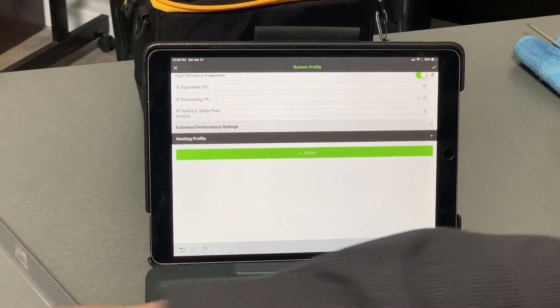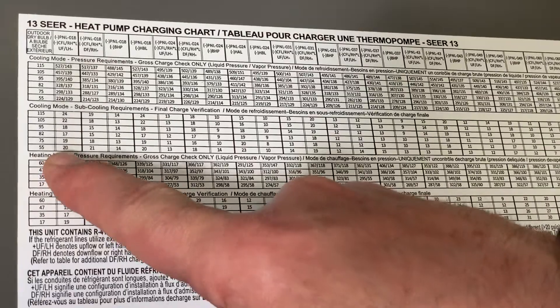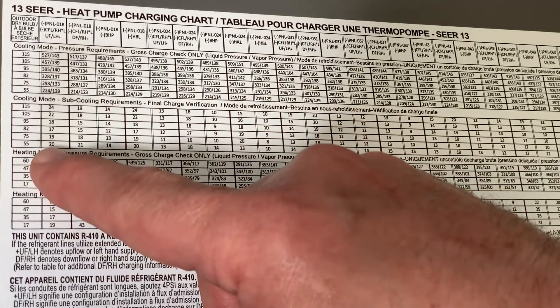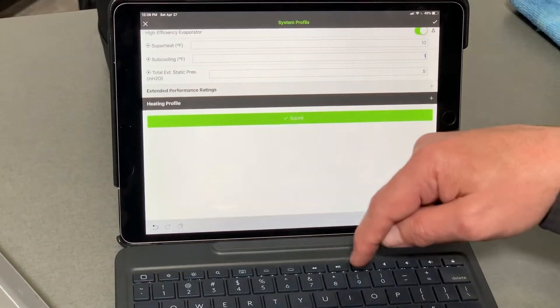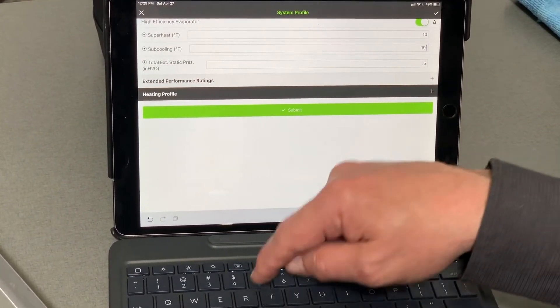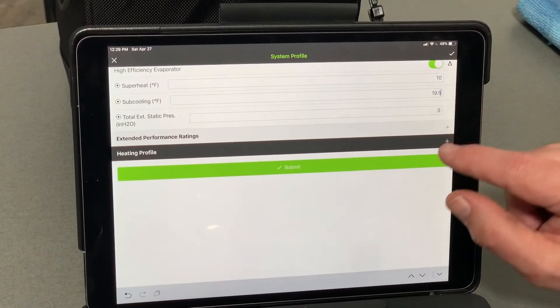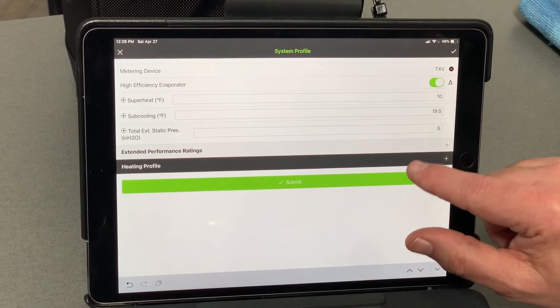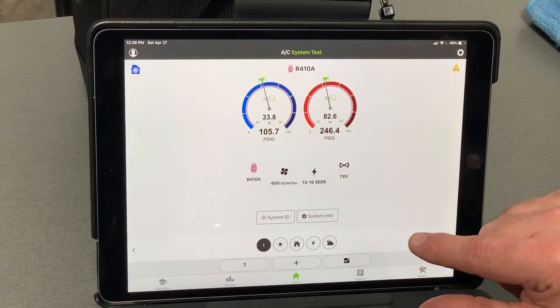For subcooling requirements, let's look at the nameplate tag. We're at about 55 to 75 degrees in here. Looking at the tag — RPNL018, upflow — we go down to the subcooling requirements. Between 55 and 72 degrees the target is 19 to 20 degrees, so we'll set that at 19 or 20 degrees — even 19.5, whatever you prefer. You can get that right down to exactly what you want. Then we enter our total external static pressure at 0.5.